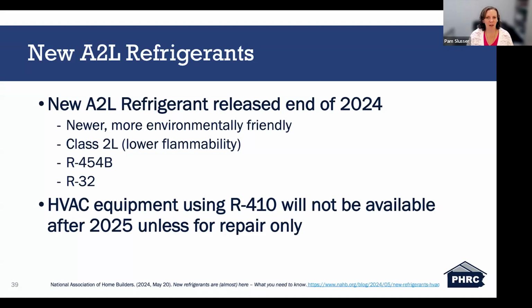So a little bit about it, the A2L is a more environmentally friendly refrigerant. It's a Class 2L labeled, which is considered lower flammability, whereas the 410A was a Class 1, which was no flame propagation, is how they were labeled. Two primary refrigerants are being used with the A2L, which are the R454B and the R32. The R454B is a blended refrigerant where the R32 is not blended. So R410A equipment will no longer be sold by the end of 2025, with the exception of only for repairs to existing units.